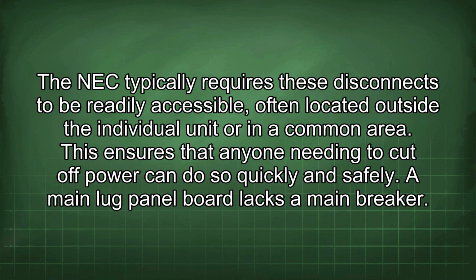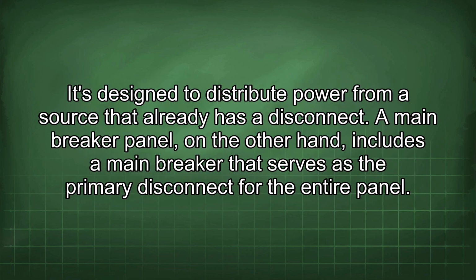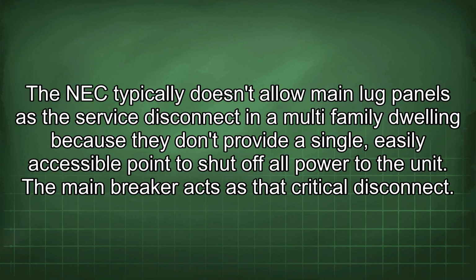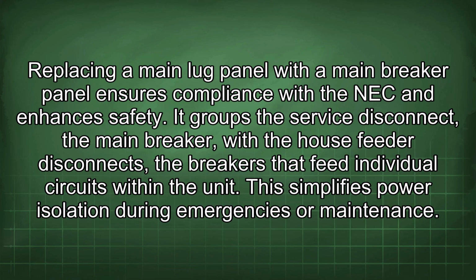A main lug panel board lacks a main breaker. It's designed to distribute power from a source that already has a disconnect. A main breaker panel, on the other hand, includes a main breaker that serves as the primary disconnect for the entire panel. The NEC typically doesn't allow main lug panels as the service disconnect in a multi-family dwelling because they don't provide a single, easily accessible point to shut off all power to the unit. The main breaker acts as that critical disconnect. Replacing a main lug panel with a main breaker panel ensures compliance with the NEC and enhances safety. It groups the service disconnect, a main breaker, with the house feeder disconnects, the breakers that feed individual circuits within the unit. This simplifies power isolation during emergencies or maintenance.